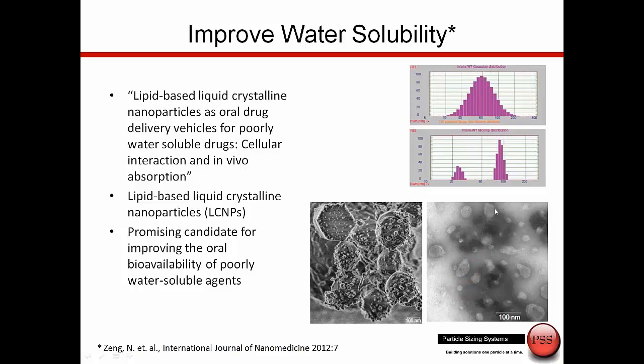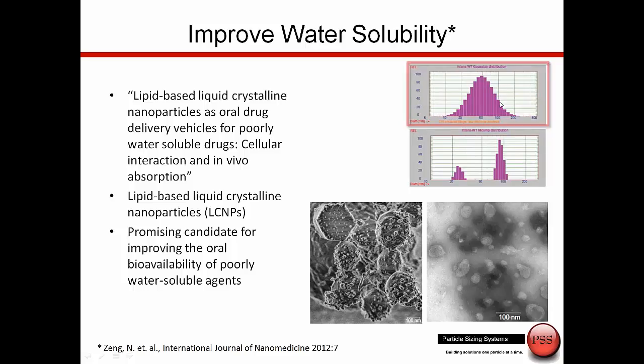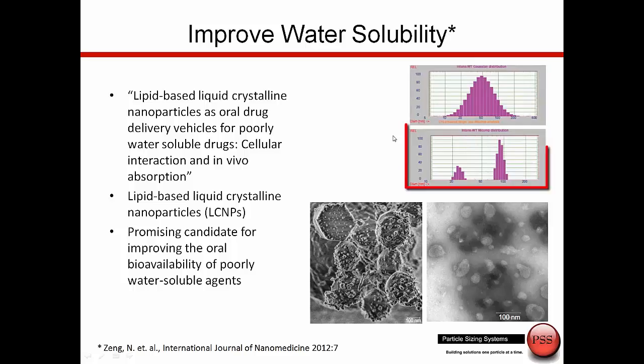So there are actually some small and some large particles. If you measure this sample using dynamic light scattering and just look at a Gaussian distribution fit to a normalized curve, you'd say it's a single population. But one of the real benefits of the NICOMP DLS system is the NICOMP algorithm — using a non-negatively constrained least squares approach, it's the highest resolution DLS system, and is able to dig out this bimodal distribution that you can see with your own eyes.